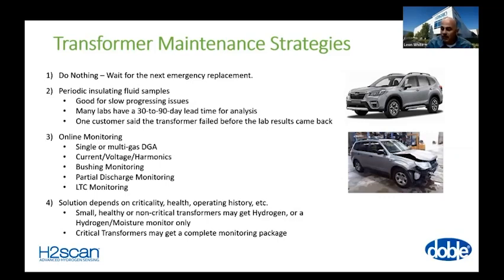Looking at the gases in the transformer oil is very important. As criticality increases, or if you have unhealthy transformers on your system, there are times when you want to go to multi-gas systems that do partial discharge and bushing monitoring and so forth. Again, vendors can provide a lot of recommendations on what you should put on a particular transformer based on what bushings are in there and what type of load tap changer it has, if any.